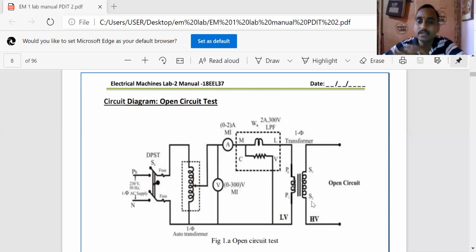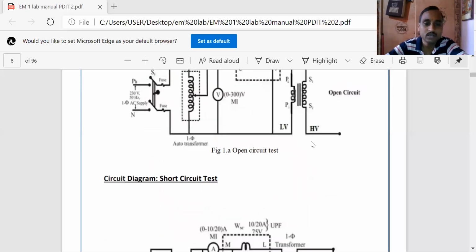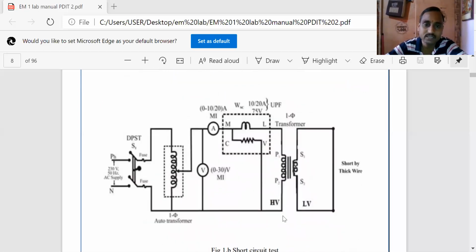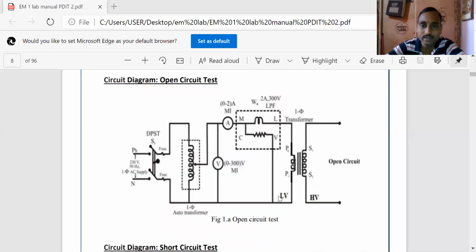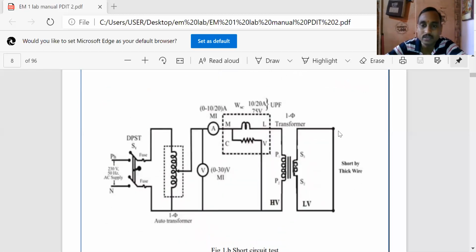So generally, the high voltage winding is kept open. In general, if you conduct an open circuit test, you connect all the meters on the low voltage side, and the high voltage side should be kept open. This is the circuit diagram for the open circuit test. For the short circuit test, the connection is the same. The only thing is, you have to interchange the low voltage winding and high voltage winding. In this case, the short circuit test is always done with the short on the low voltage winding, and you need to connect all the meters near the high voltage winding. So that is the only change.